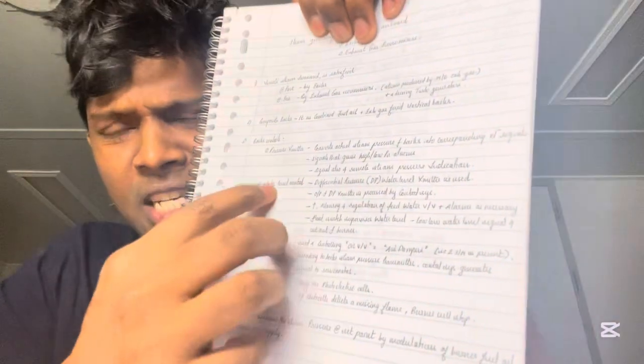But other than this, I'll give you some additional points as well. I made some notes on boiler controls which I wanted to share. There is something called a differential pressure transmitter, or DP transmitter. The output of the DP transmitter regulates the feed water and raises alarms as necessary. There is a float switch that monitors the level of the water, but the regulation of water inside the boiler is done using this DP transmitter.